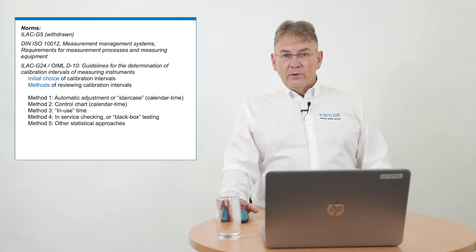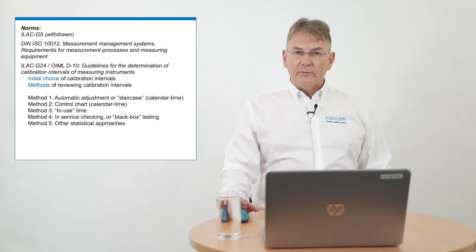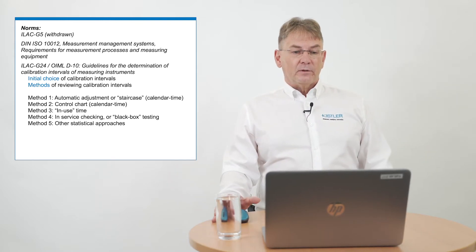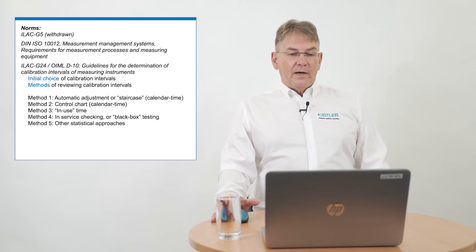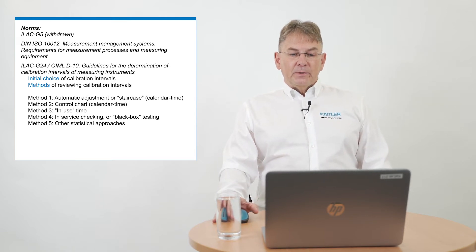What we can do is dig further into applicable norms and specifications. We found ILAC G5, a norm which has been pretty good and gives helpful hints for everyday work, but it's unfortunately withdrawn. We have the DIN ISO 10012 measurement management system — requirements for measurement process and measuring equipment — but it doesn't really help; it's very global. But we found something else: the ILAC G24-OIML D-10, which is called guidelines for the determination of calibration intervals of a measuring instrument.